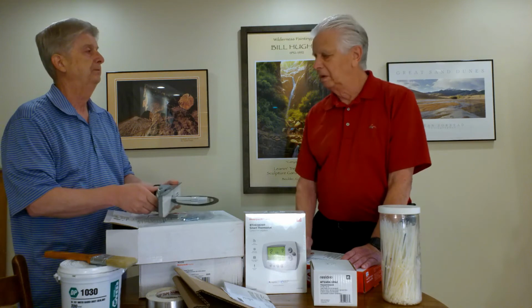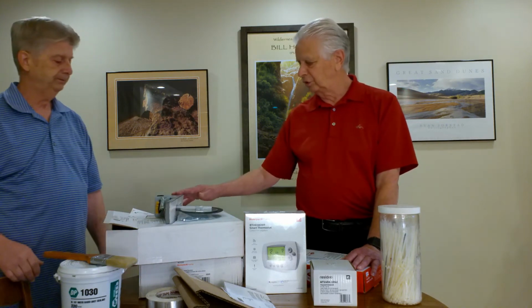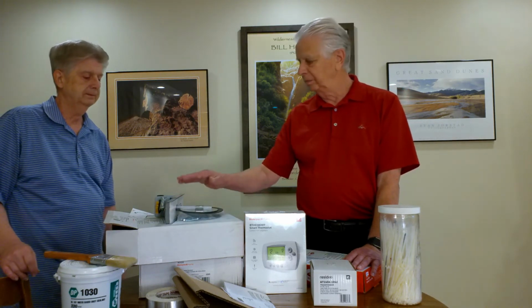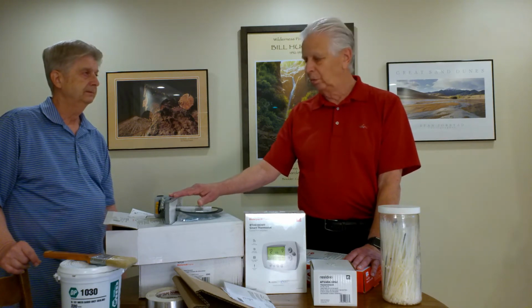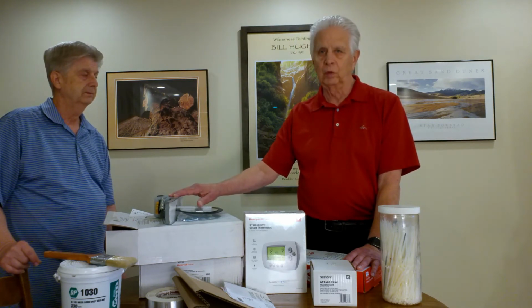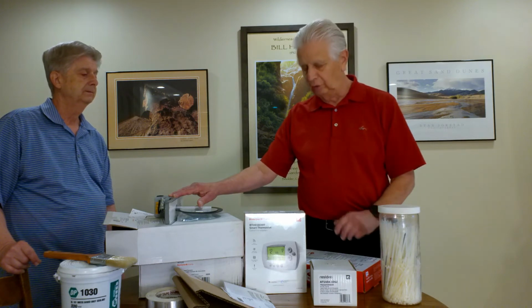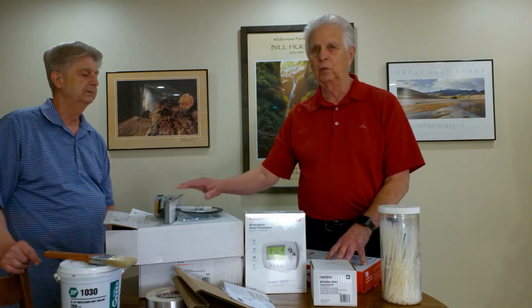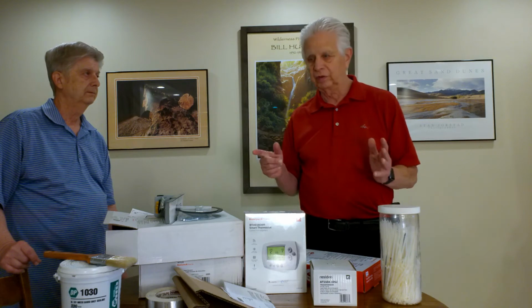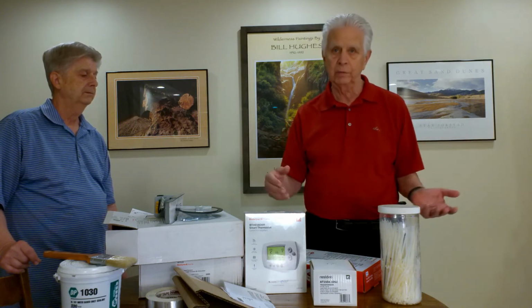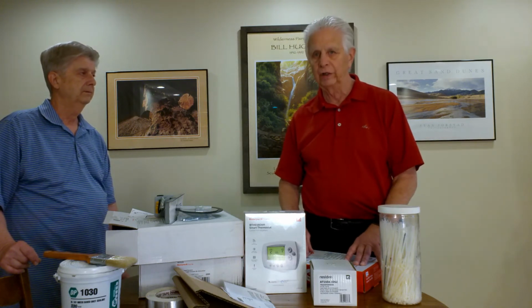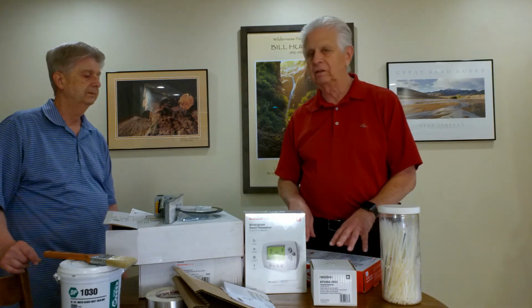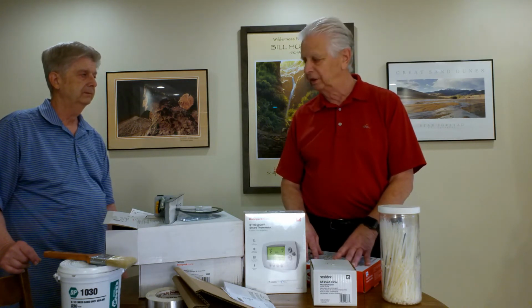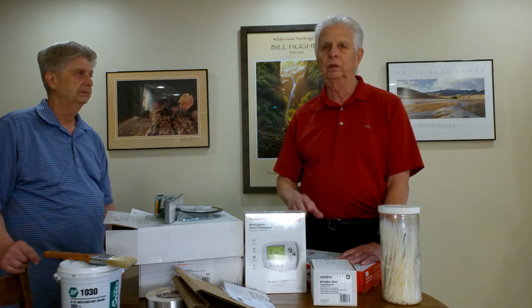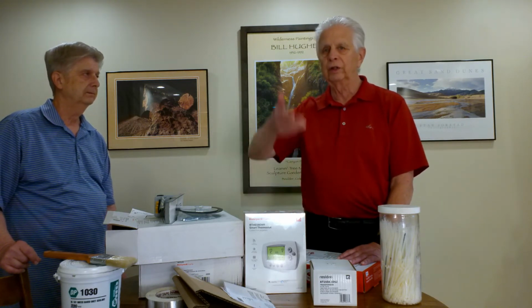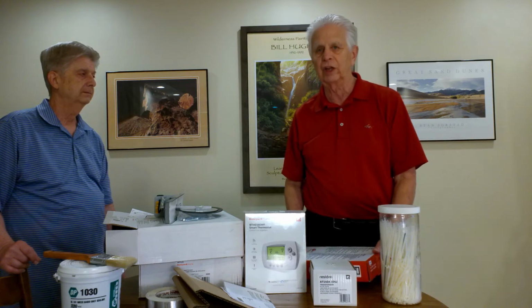Yeah. I might mention on our situation, we only put dampers on the first floor, although the zone control panel will handle dampers on the second floor, would handle dampers for the basement if you wanted. But to get the balance we wanted, we only needed to close enough down on the first floor to pull the air up to the second floor.